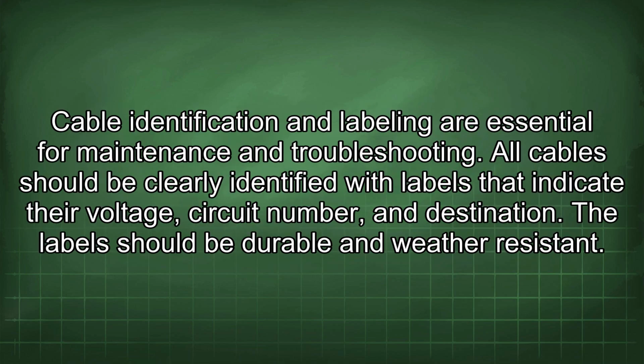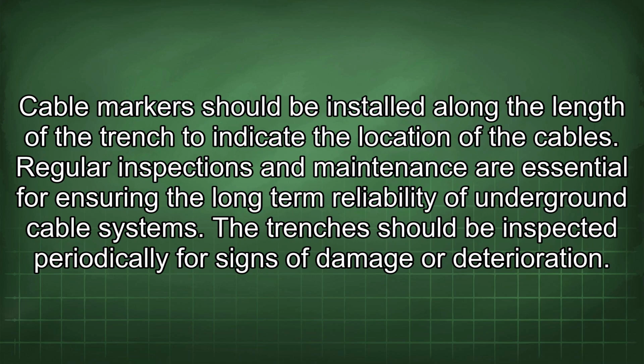Cable identification and labeling are essential for maintenance and troubleshooting. All cables should be clearly identified with labels that indicate their voltage, circuit number, and destination. The labels should be durable and weather resistant. Cable markers should be installed along the length of the trench to indicate the location of the cables.